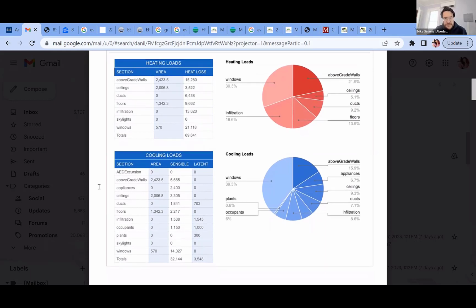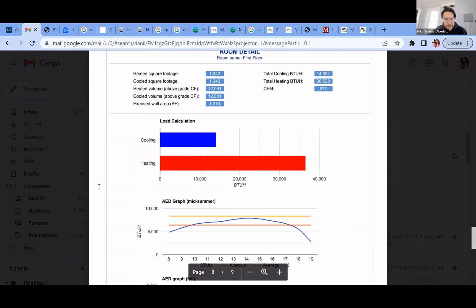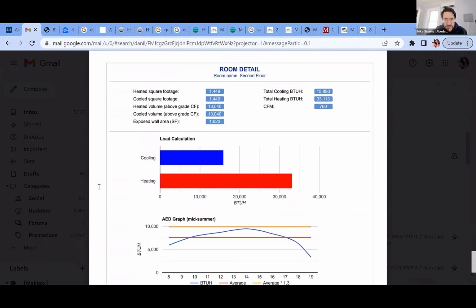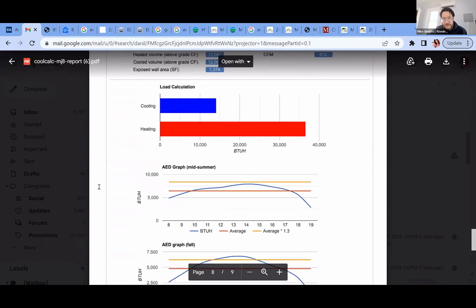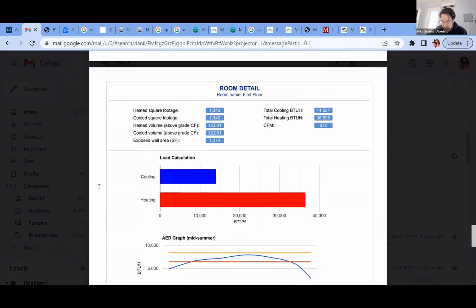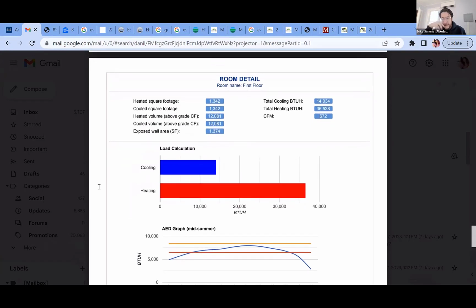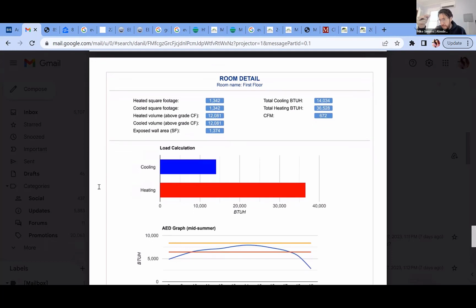You want to scroll way down on the report? Keep going. So for the second floor, they have the second floor's total heat load as 33, and I go up a page to the first floor. Over here, they have the first floor's heat load at 36. My feeling, as a building scientist, is that you do have bigger square footage upstairs with the room over the garage, so it still feels slightly unbalanced. The first floor is probably fine; the second floor is where I'd probably try to hone the numbers in.